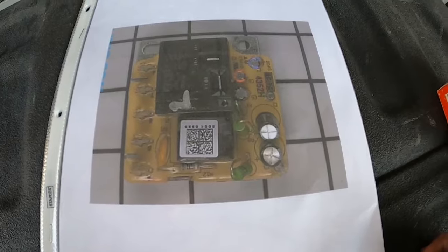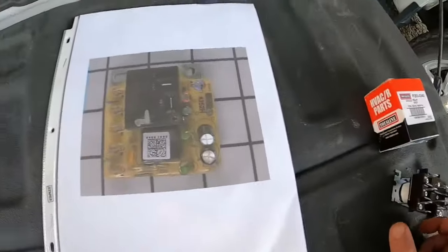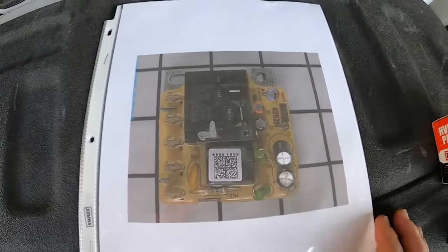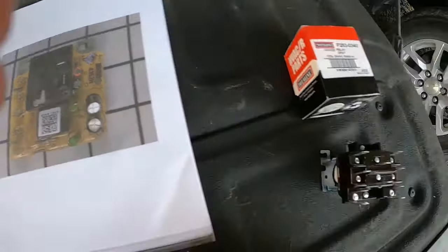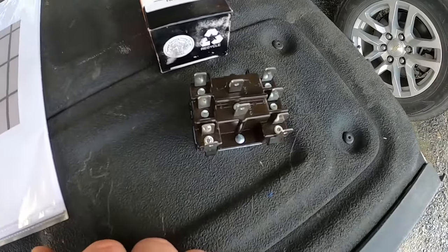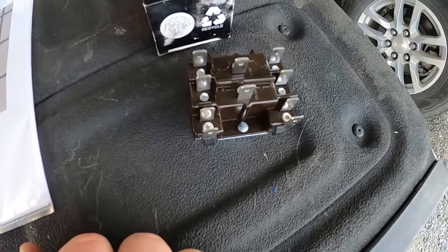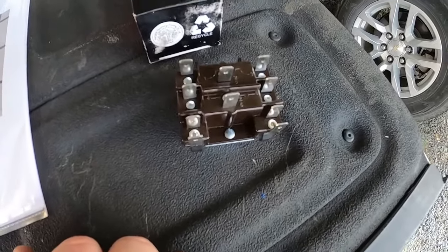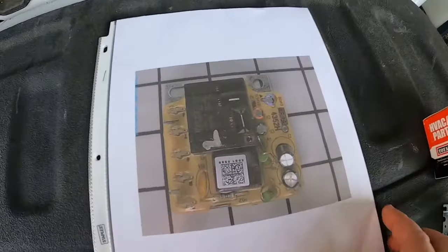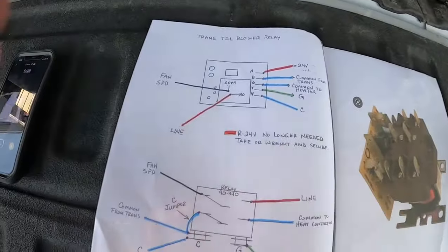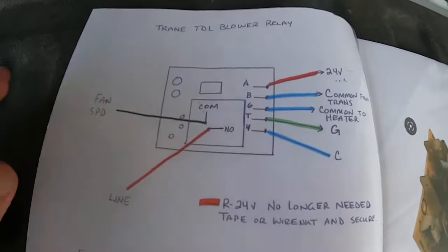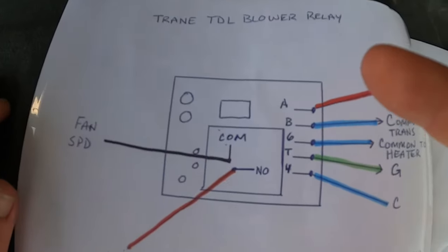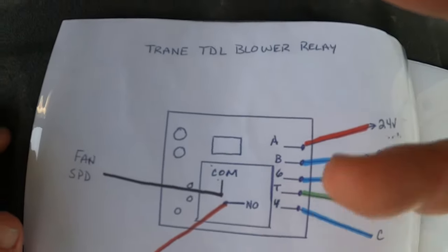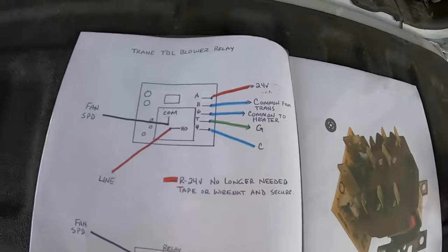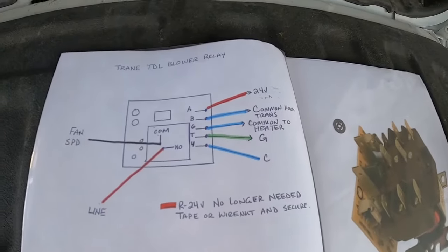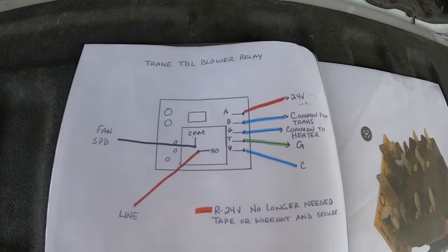And you know, even if you don't have this relay, yes, that's an option to get that unit running until you can get a response for them. But most everybody's going to have this on their truck, so there's no reason why you can't go out and grab this, come in here and replace this control board and that blower relay control. This is how it lays out. I've got everything labeled the same way it's labeled on that board, and it's going to give you all the options you need.